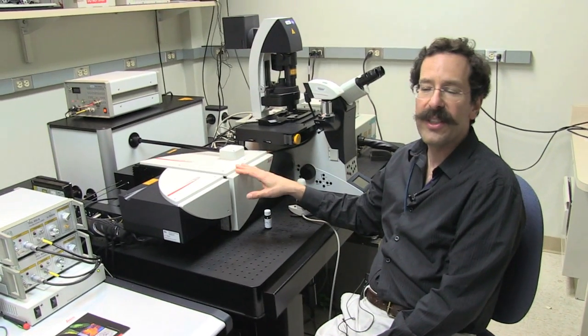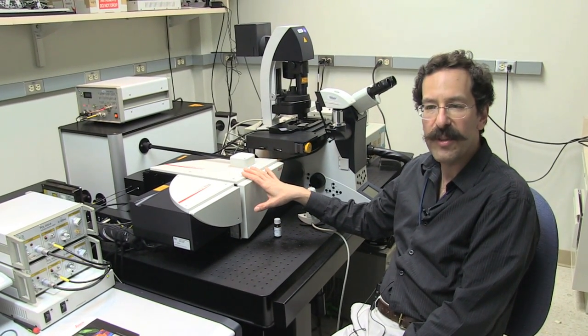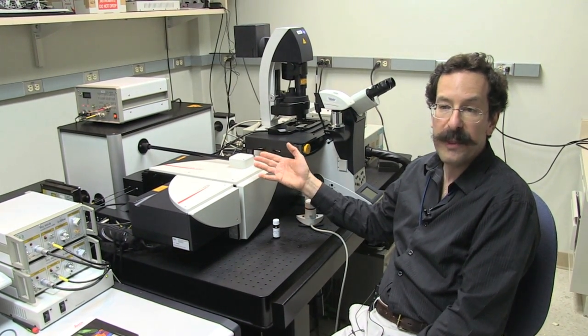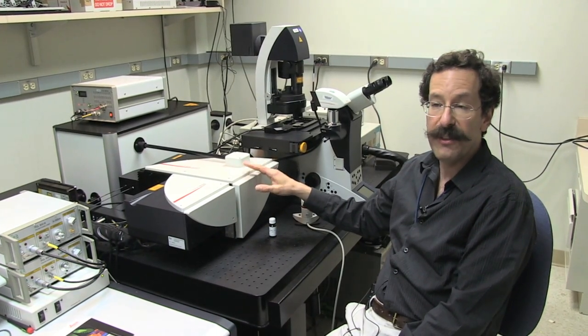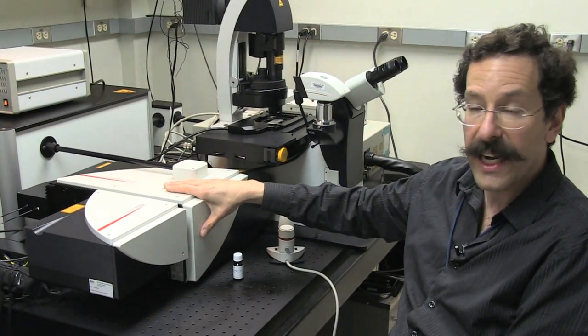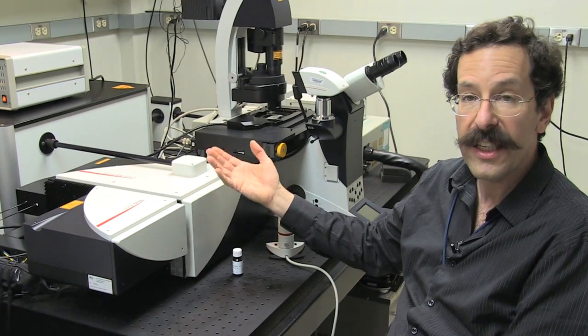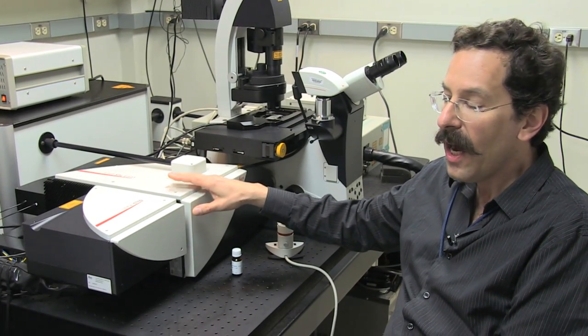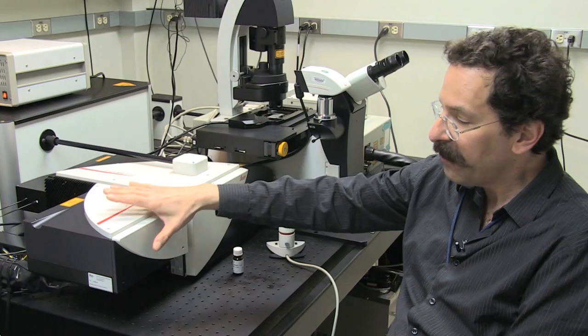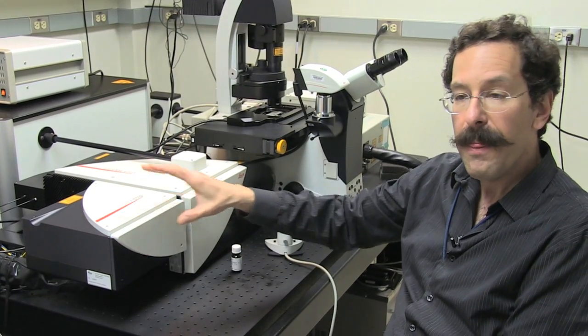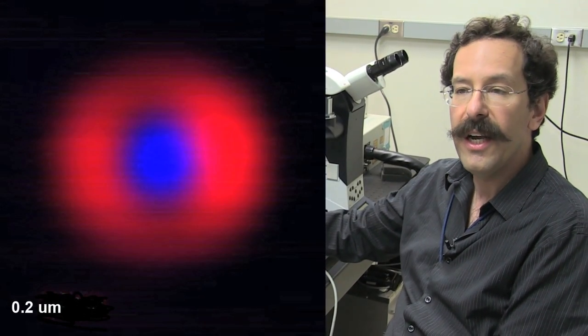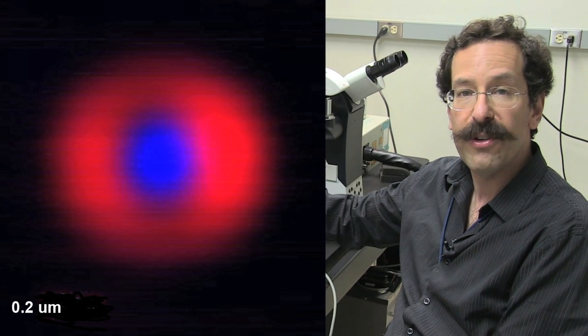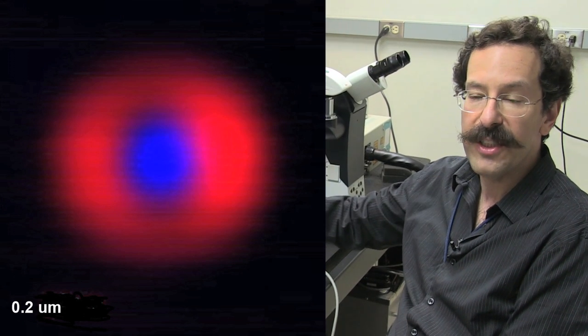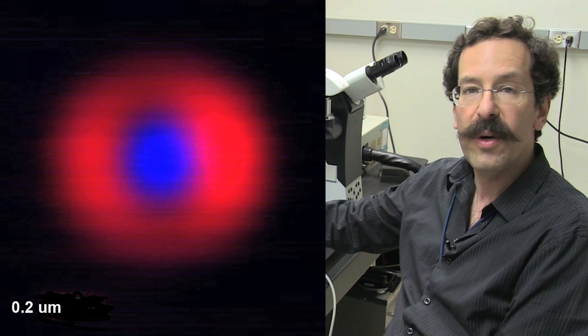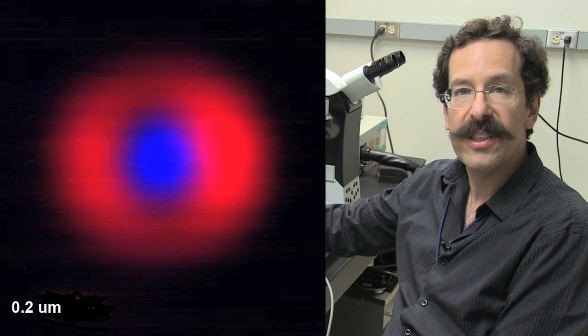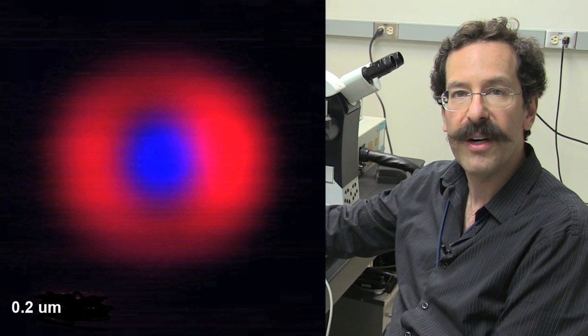The way it actually works is, there are two laser beams that are turned on simultaneously. The conventional one, which would be blue or green or red, visible light would come through the standard confocal scanner, go into the microscope and excite the fluorescence, make the sample glow. Superimposed on that is an infrared beam that comes through this component here. The infrared beam is shaped into a donut, and it serves to actually turn off the fluorescence or deplete it in the regions of the donut. And in the hole in the center, what's left is purely the in-focus light at a higher resolution than we had before.